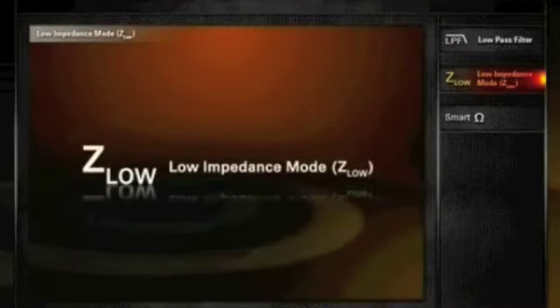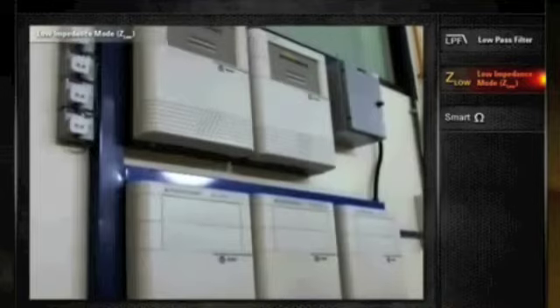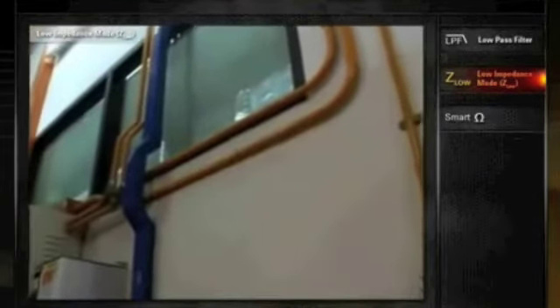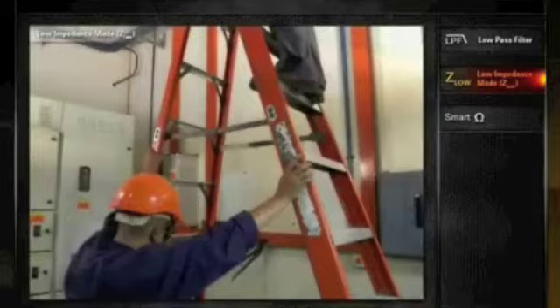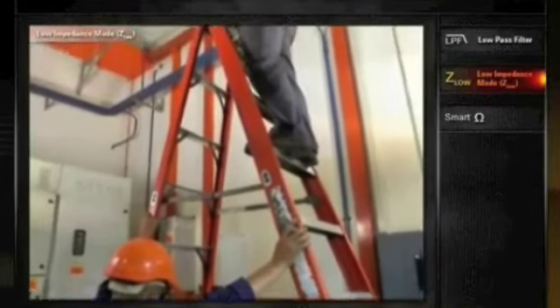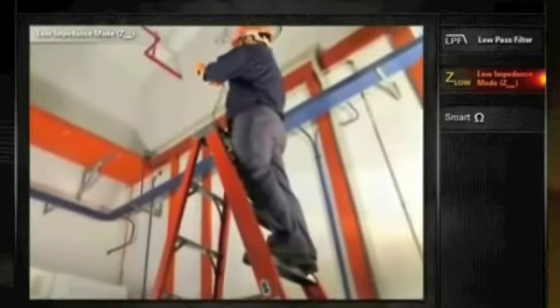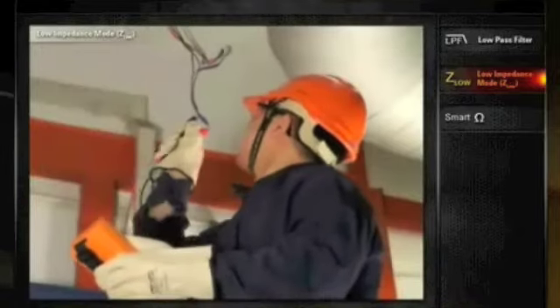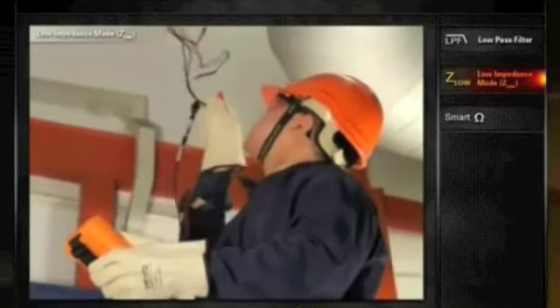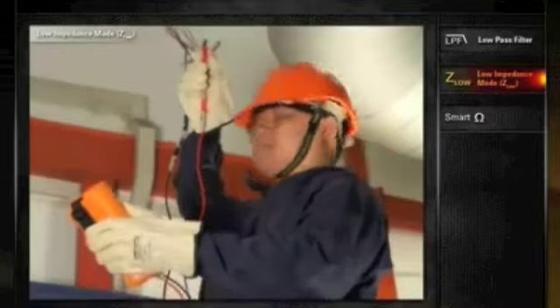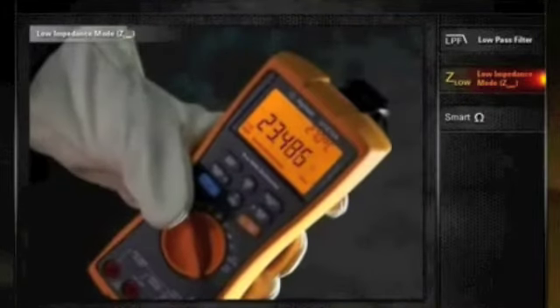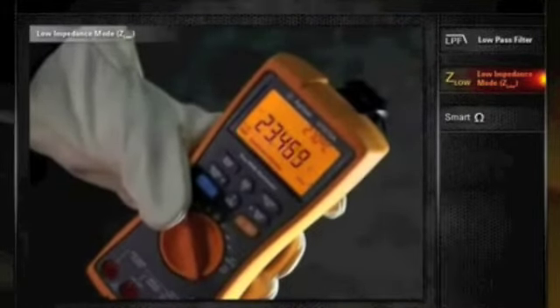Low Impedance Mode, Z-Low. Electrical conduit is commonly found in many buildings. They protect enclosed conductors from moisture, chemical vapors and impact. Although the conduit is safe and convenient, high-input impedance multimeters can pick up stray voltages on unused wires that run parallel with energized wiring. As you can see, we currently detect a voltage reading on the unused wires.